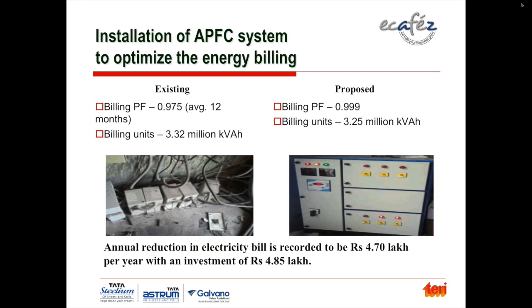You can see they had some sort of capacitor bank before, obviously, which was not taking the power factor to 0.999. With installation of a new automatic power factor correction panel, as you can see, they can maintain 0.999, and the billed units have come down to 3.25 million kVAh. The electricity bill saving is about 4.7 lakhs per year with an investment of 4.85 lakhs. So this is a very simple tool to save energy immediately in the plant through power factor correction, wherever the billing is based on kVAh.